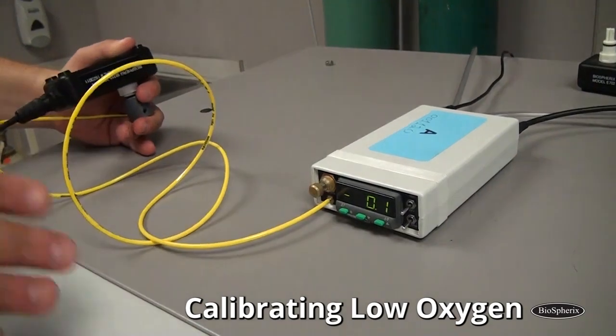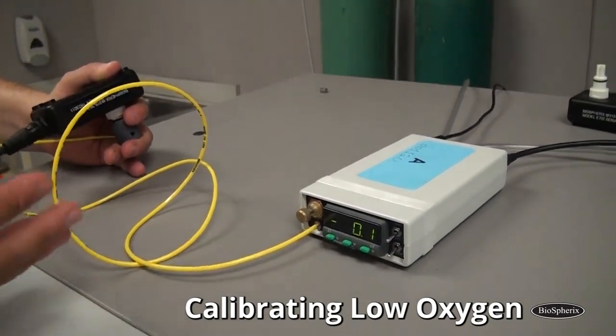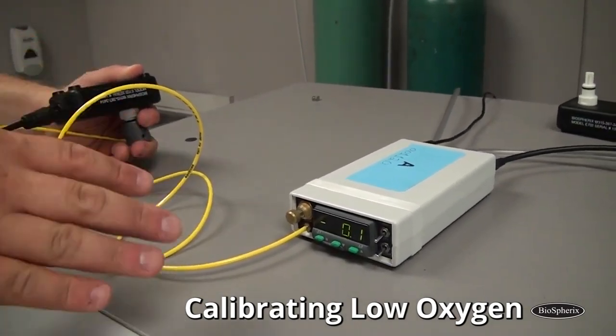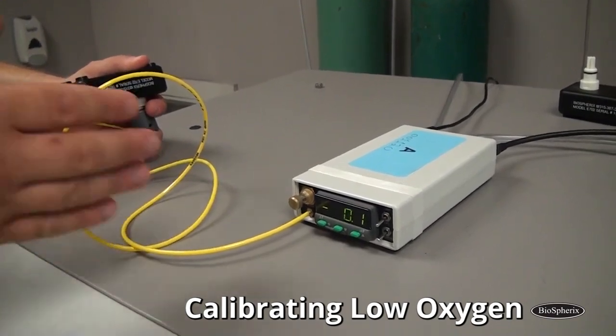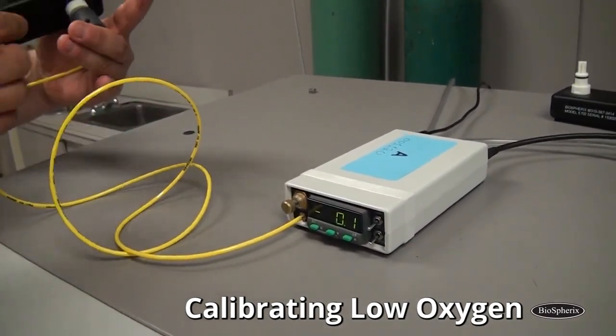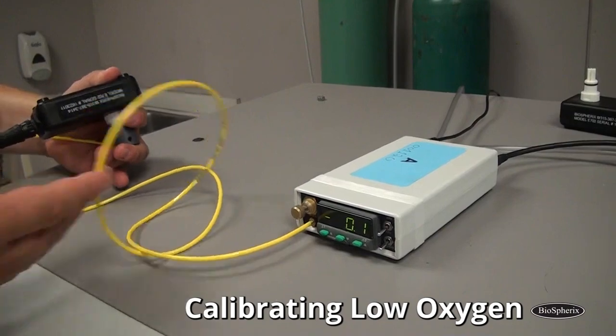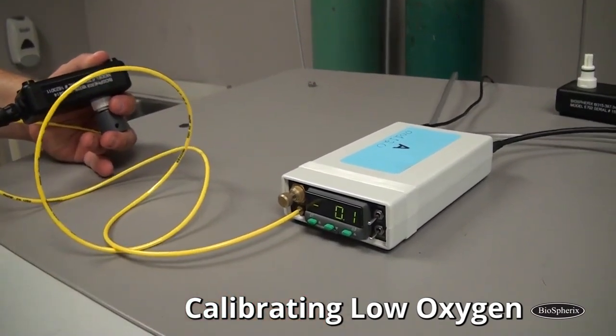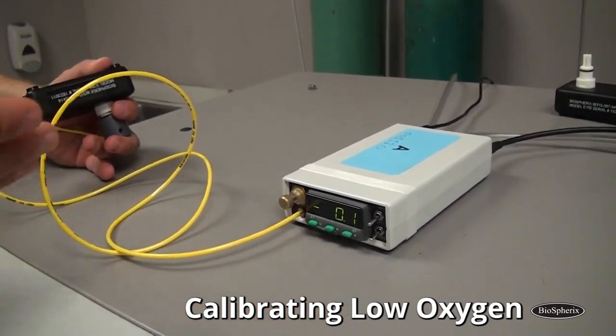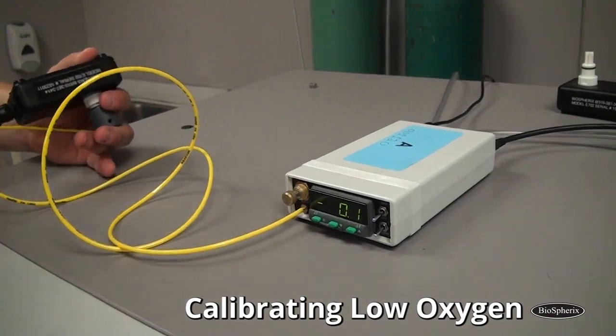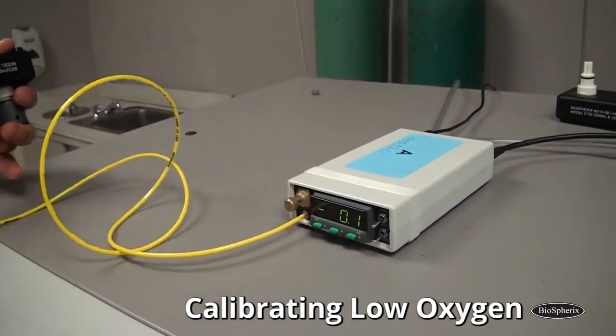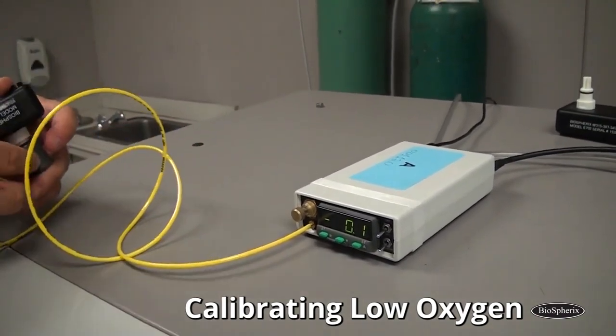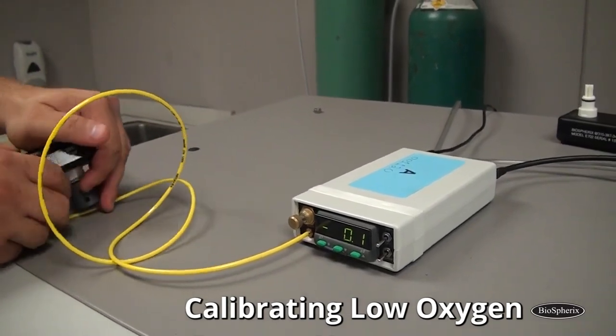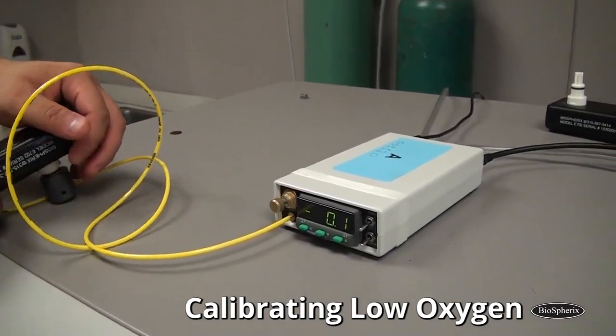Okay, so I wanted to show what would happen if it doesn't settle right at zero. So we've got our nitrogen flowing right over the tip. It's stable. I've let it run about 2 minutes, and it says minus 0.1. That's incorrect. It should be 0.0. It's pure nitrogen. Can't be a minus. So I need to make an adjustment.